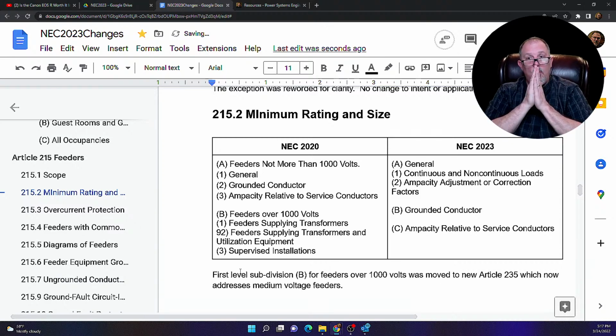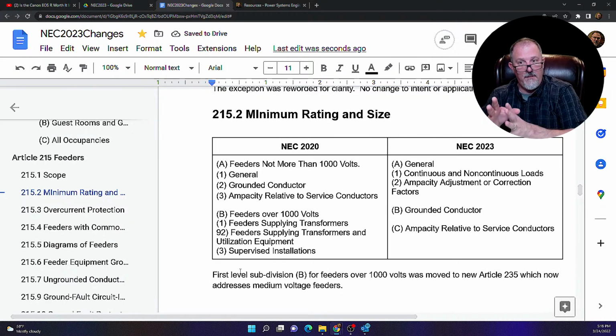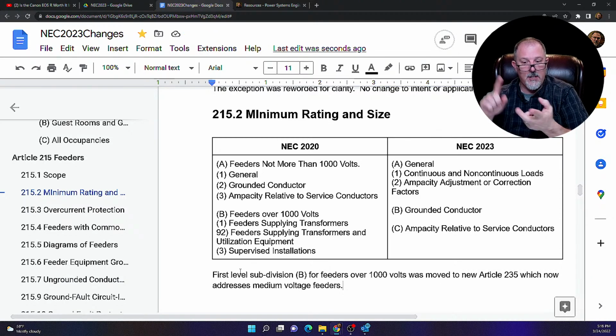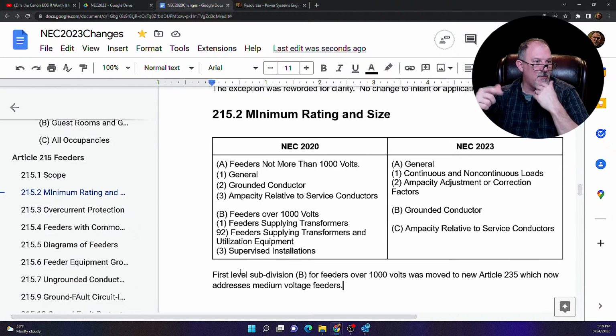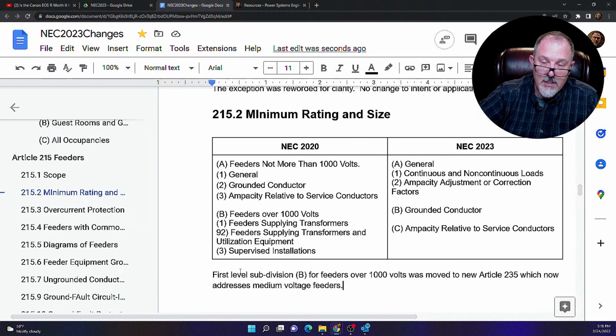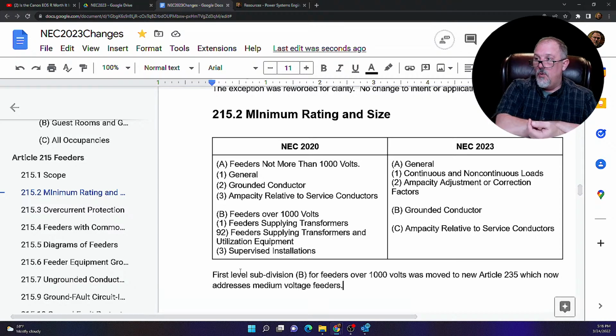Okay, so we created 235 for medium voltage branch circuits, feeders, outdoor feeders, and services, I think. We'll take a look at what the new title is for that. So that means B, all of B got moved. So there's no more B. Now we have just A, and you can't have one first level subdivision. So now the entire 215.2 only deals with feeders not more than 1,000 volts.